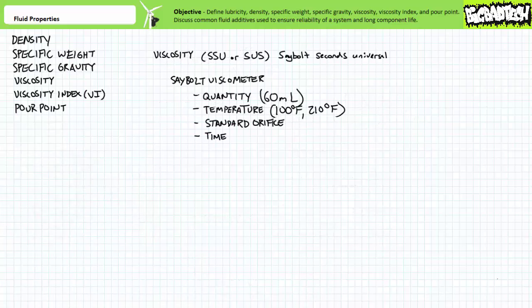Viscosity is a measure of a fluid's thickness or resistance to flow. There are several means of measuring viscosity. However, industrial viscosity measurements are typically expressed in units of SSU, or Saybolt Seconds Universal. Viscosity being characterized by a unit of time, the second, might seem odd at first, but it's an excellent description of a fluid's thickness or resistance to flow.